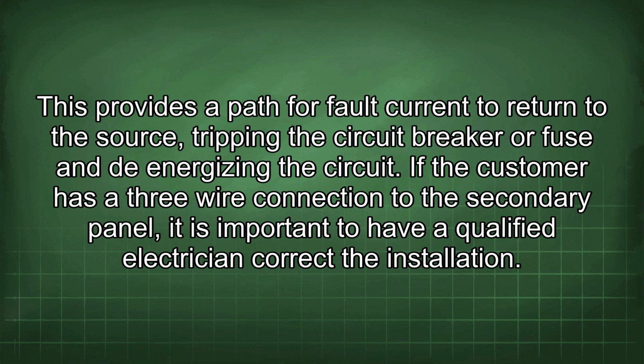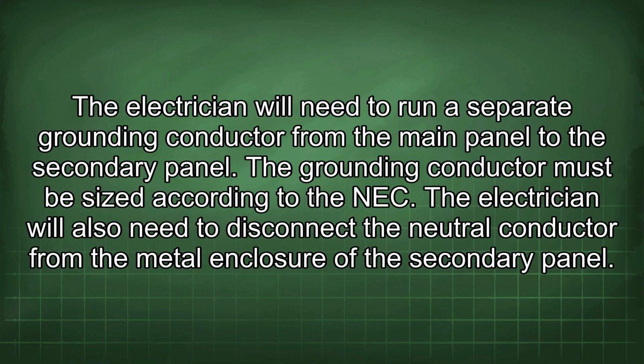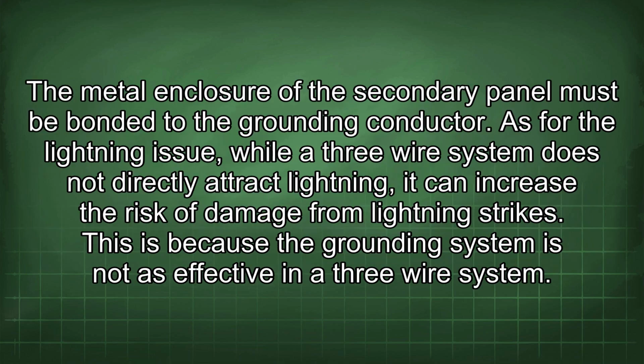the circuit. If the customer has a 3-wire connection to the secondary panel, it is important to have a qualified electrician correct the installation. The electrician will need to run a separate grounding conductor from the main panel to the secondary panel. The grounding conductor must be sized according to the NEC. The electrician will also need to disconnect the neutral conductor from the metal enclosure of the secondary panel. The metal enclosure of the secondary panel must be bonded to the grounding conductor.